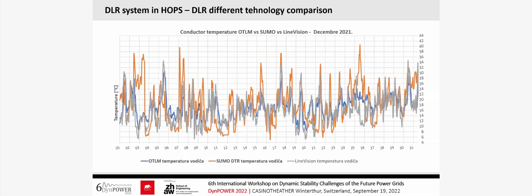You won't have the exact same temperature from those three systems because they work differently, but the software-based one is good enough and tends to be on the safe side, giving a higher temperature, meaning a lower DTR limit, which keeps you safe when operating the line.